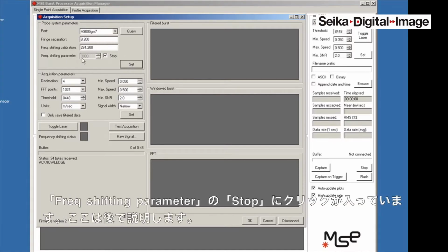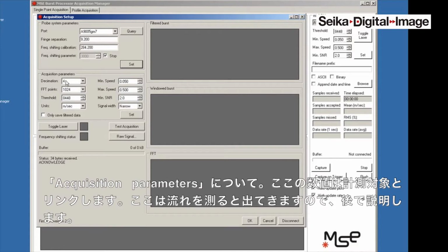In here there's a frequency shifting parameter that shows the stop is on. That means the frequency shifting instrument is off because we've stopped it. I will come back here for this value later. The second group of parameters are the parameters that relate to the flow, and we will get that once we set the flow up, and then I'll show you what these numbers mean and how to set them up.